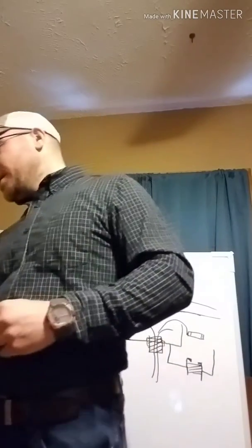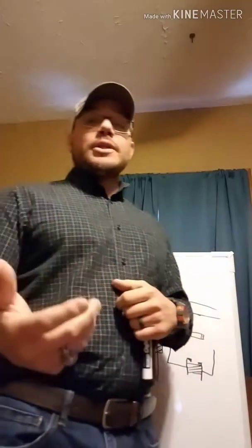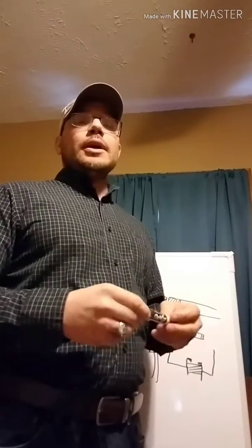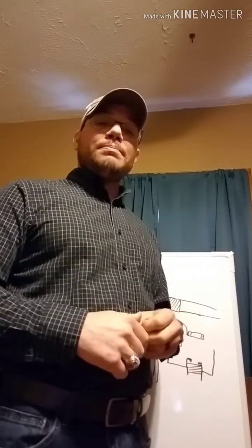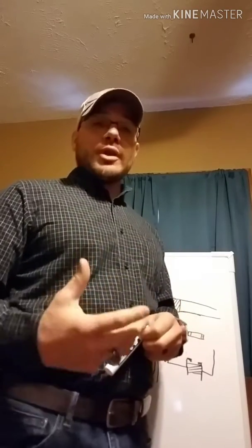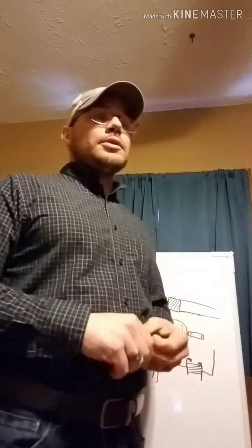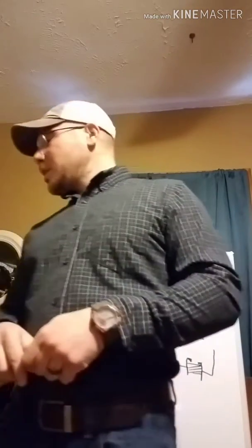Okay, and of course 342.60 is grounding. IMC shall be permitted to be an equipment grounding conductor. Okay, so we can use that as the equipment grounding conductor itself. We don't have to pull a ground in. Again, what I always say is pull it in anyways, right? Now, IMC is a little bit different than EMT because of the fact that the RMC is normally threaded. So I'm more comfortable using the conduit as a ground if everything is threaded. But I still would suggest pulling a ground in. Just know that IMC can be used as your grounding conductor. Excuse me.